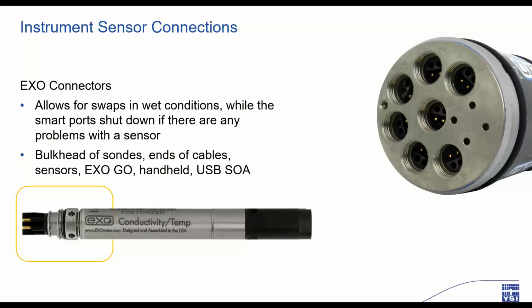Regarding the bulkhead ports, you can actually fill up the port with vinegar, like little cups, and let this sit for about 10 minutes. Then using a pointed Q-tip, gently rotate the Q-tip around and help free up the old grease and debris. Never force the Q-tip down into the hole, as this could damage them. Then feel free to flush these ports out with water and then wipe them down gently with a lint-free cloth. Now, using a stiff bristle paintbrush or a flux brush, apply a dab of Krytox to the brush and then to the bulkhead ports. This brush will allow you to get the grease into areas that your fingers can't reach. The connectors on the base of the EXO sensors can just be wiped down with a lint-free cloth, and then again, using a small paint or flux brush, apply a new coat of Krytox grease to the connectors.